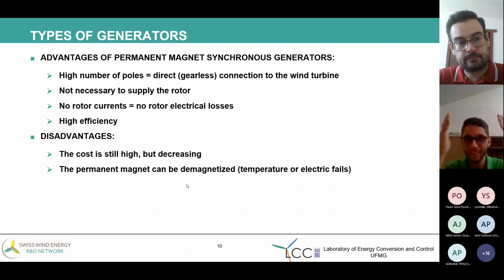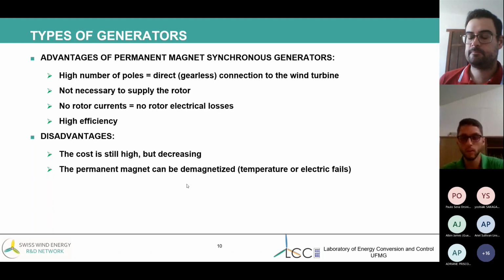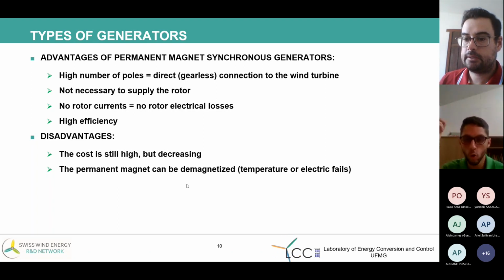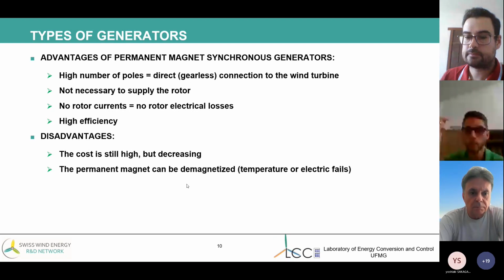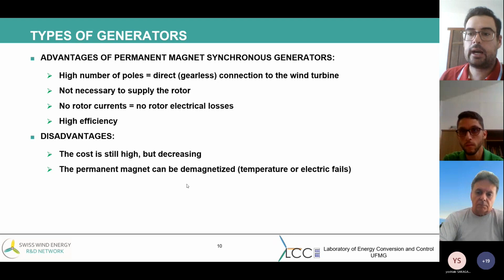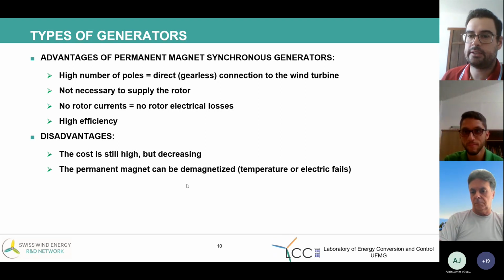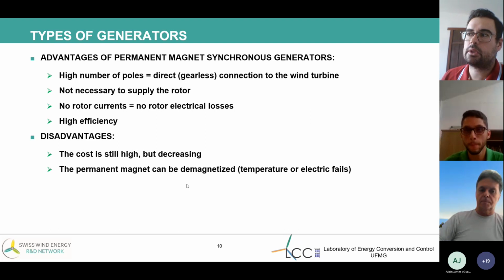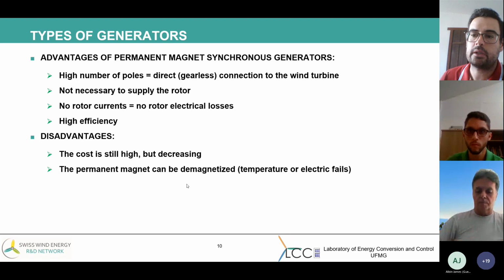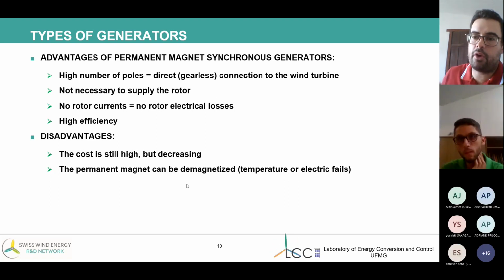As you said, a permanent magnet can be demagnetized. So in such generators, synchronous generators, we have a cooling system. I have a question. Is the cooling system to cool the magnets or the winding? Oh, the cooling system is for the whole machine. There are different types of cooling systems. We have systems cooled by wind, and it's not uncommon to have systems cooled by water, just to avoid this kind of problem.